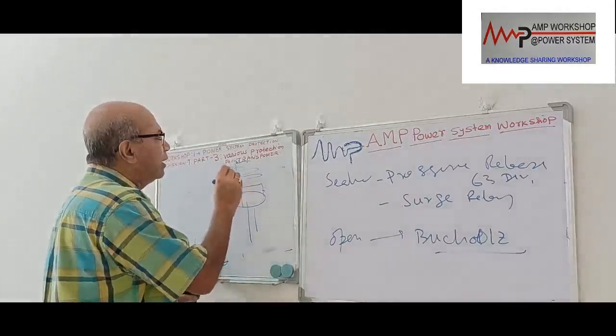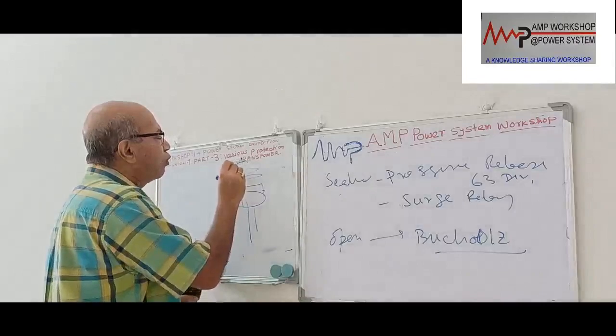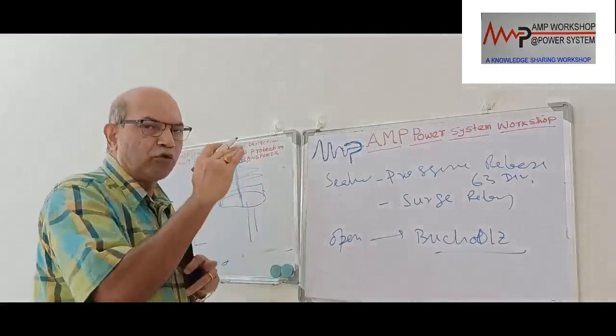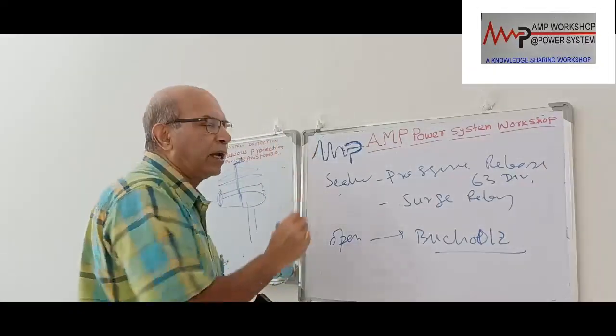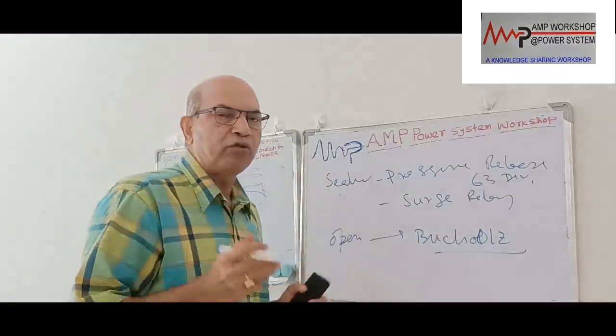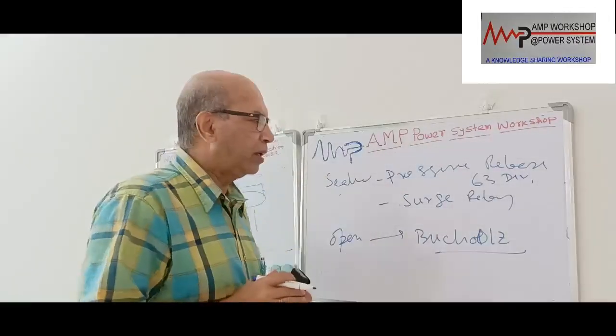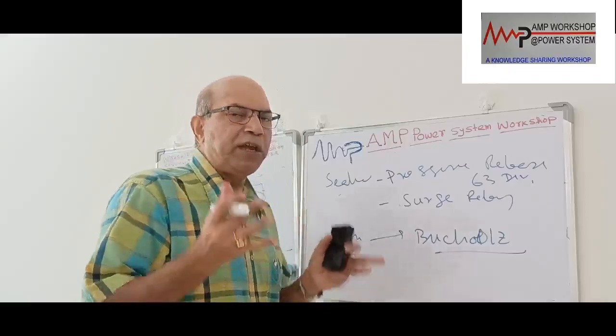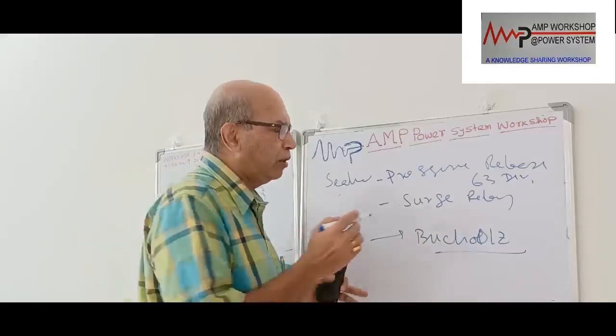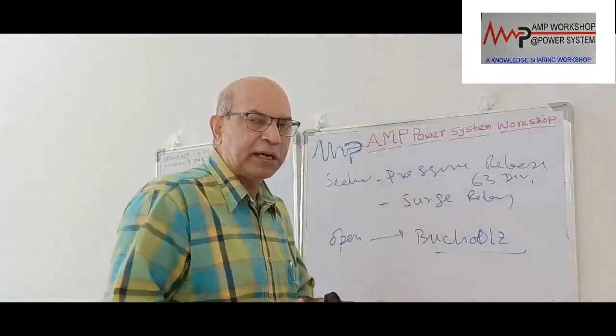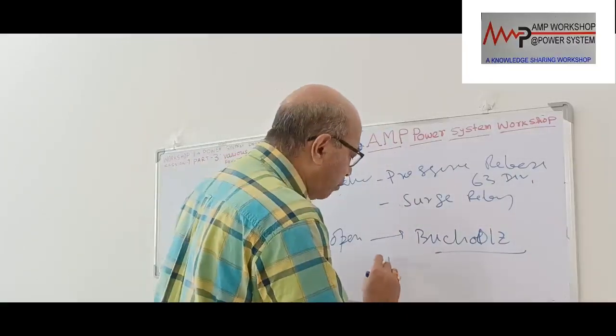On this gauge there is a snap switch which operates a pin. And that pin will open, and immediately all the gas in the transformer tank will be released from the pressure. But if this is a very heavy fault, a heavy short circuit between the windings or among the three windings inside the tank, then an oil wave will be produced.